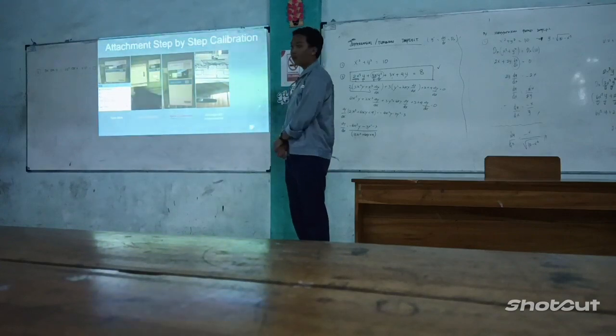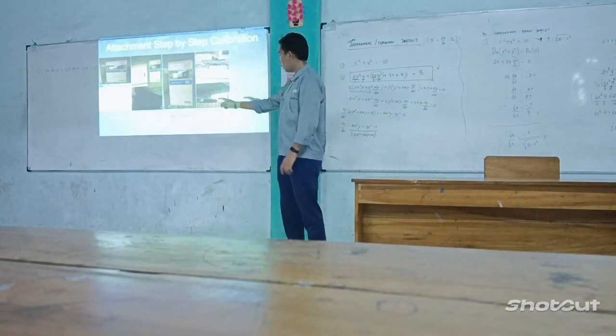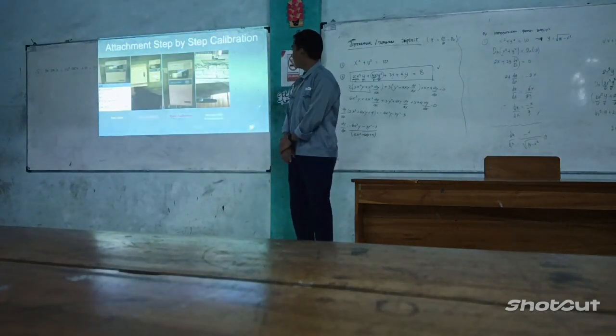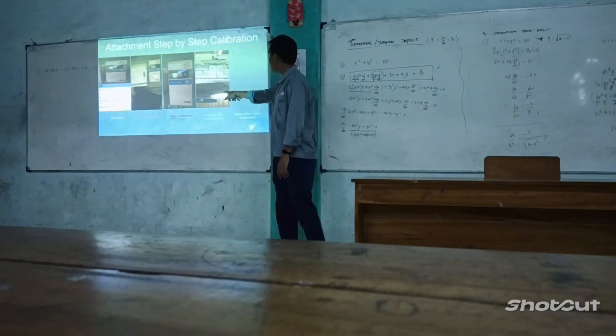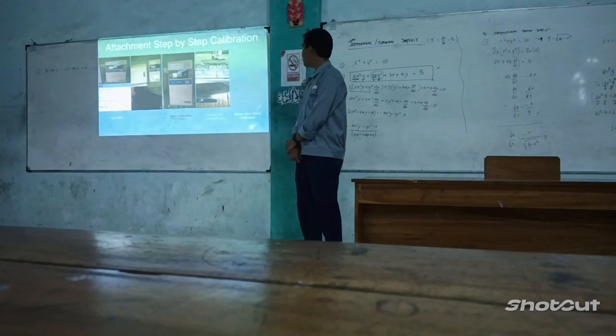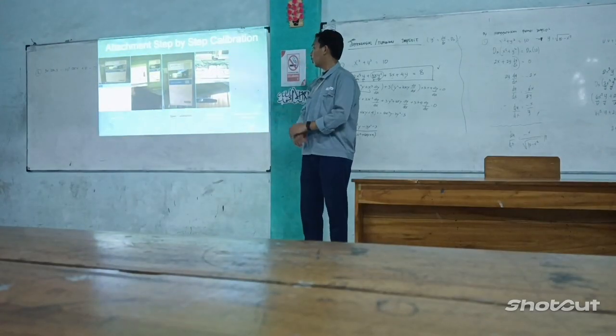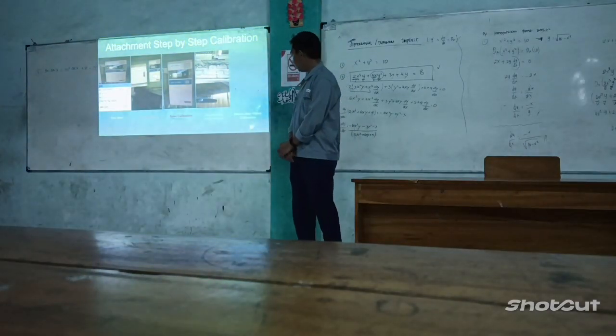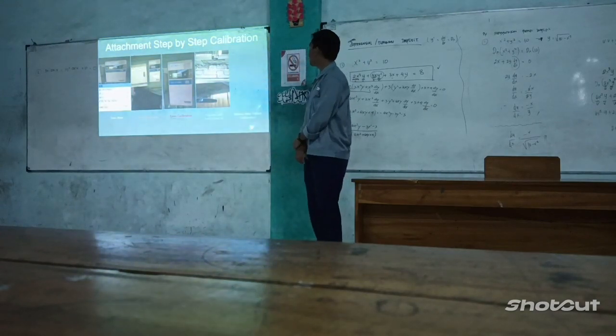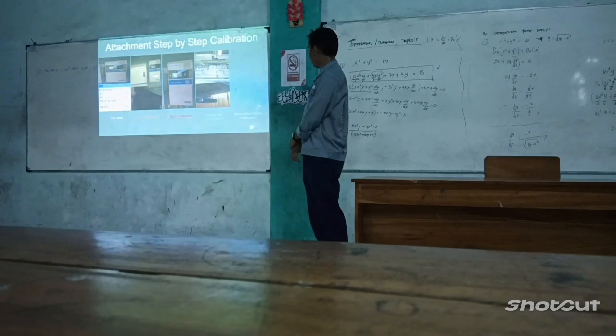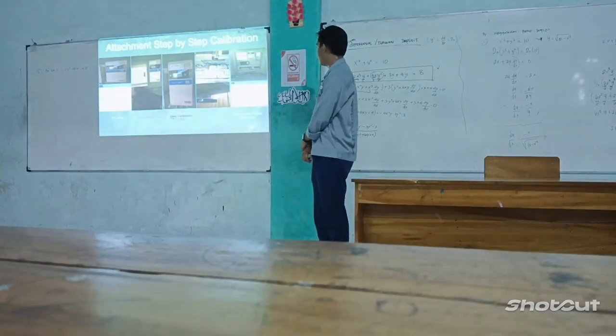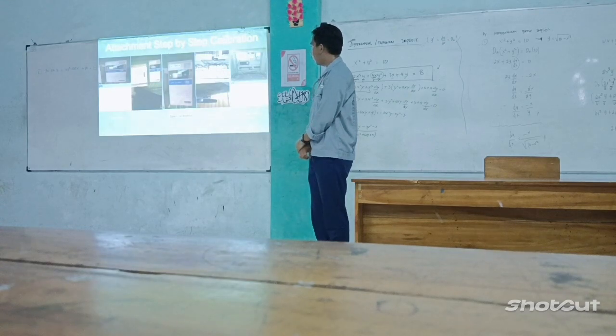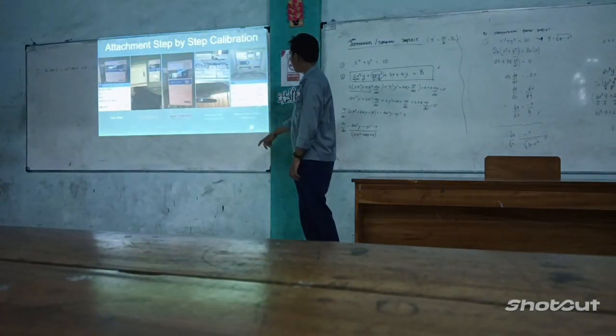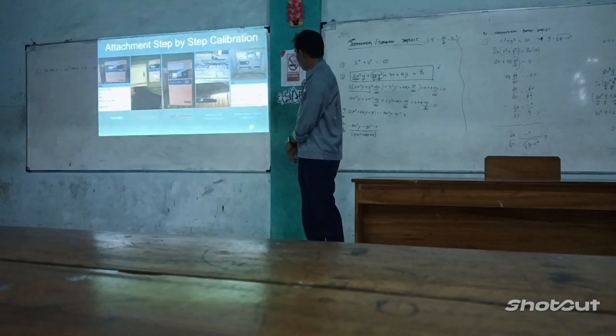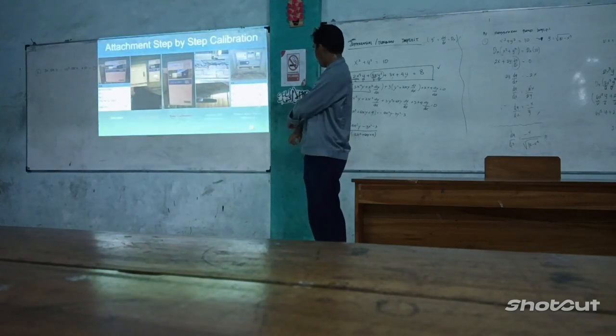This is a visual for blowing instrument air. After the zero and span calibration finish, the last step is blowing with instrument air in the sampling gas. The purpose is to prevent line clogging. We blow with instrument air, and the last step is written after calibration. After calibration, the technician gets indication 0 is 0, span for 21%, and indication 1%.